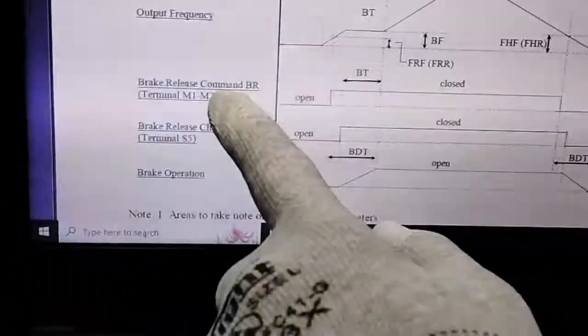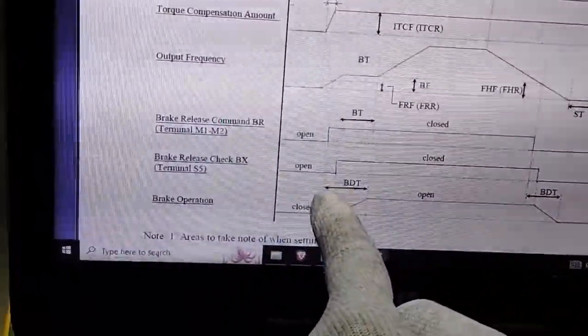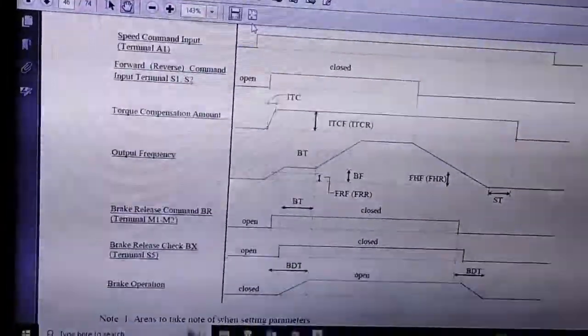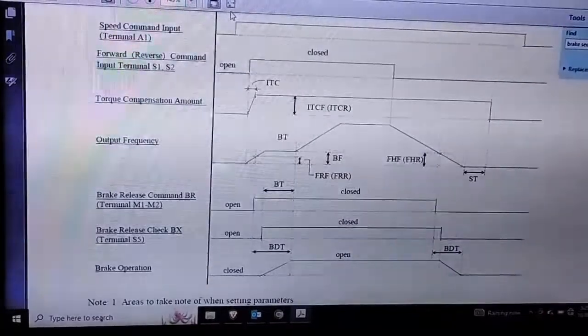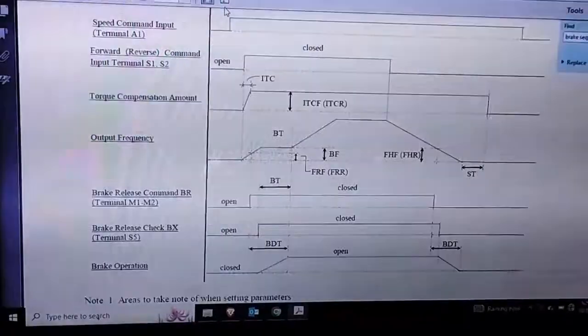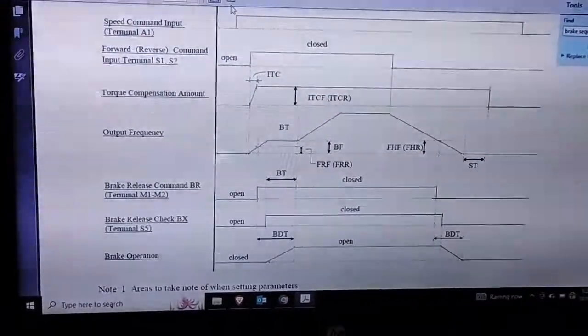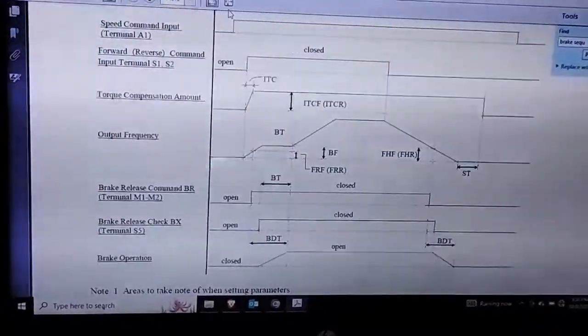We currently don't have an actual brake and contactor, but this is just to show you the concept. When you issue a run command, frequency starts increasing, but the brakes will open only after a certain point in time — after your torque and all prerequisites are achieved. We give thresholds for torque, frequency, and current, and once they are achieved, then only the brake will open and the motor will start running.